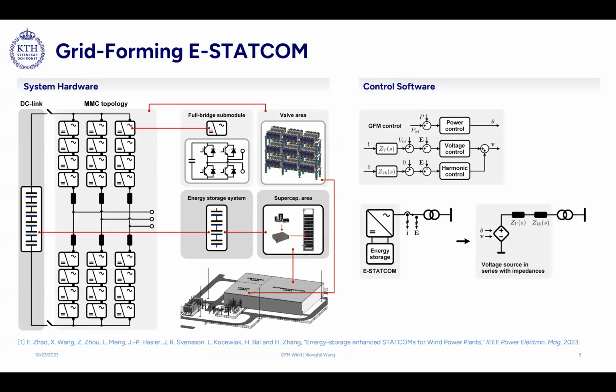And here is the control software. We use the grid forming control with basic power-based synchronization. And we also apply the virtual impedance for the voltage regulation and output impedance regulation, as well as harmonic control.